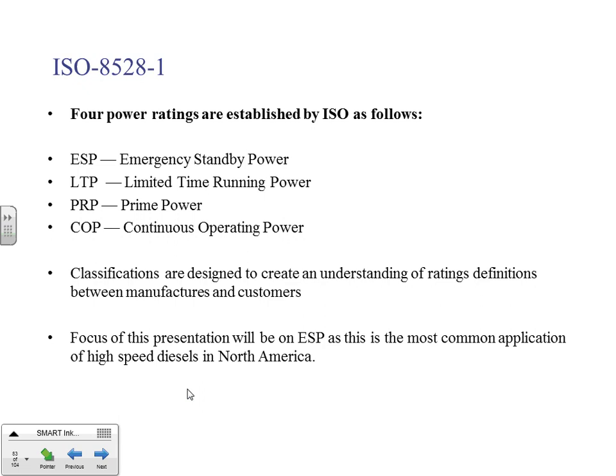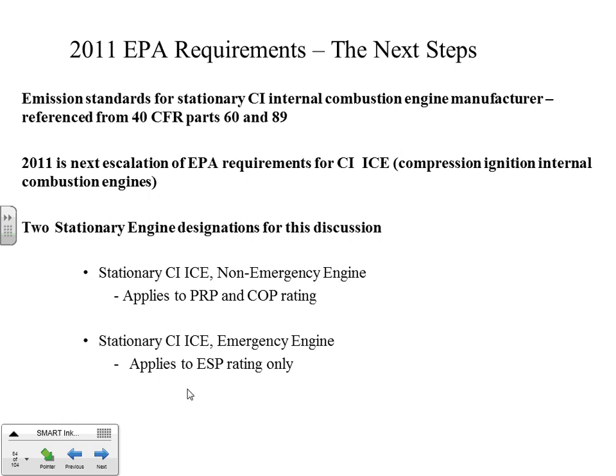This was redone in 2011 by the EPA in this standard. EPA actually redefined what we call emergency generators and non-emergency. It made only two distinctions now because of this ruling. An emergency is basically what it's always been. Standby, the true standby, where the utility fails, generator runs, and then utility comes back, it transfers back. That's true emergency.